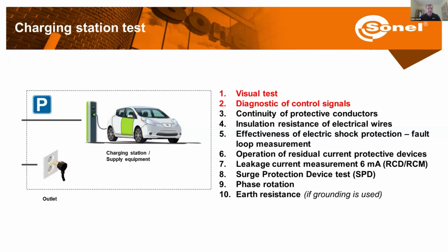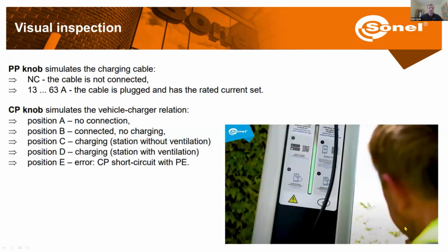Okay, so first let's start with the visual inspection and diagnostic of control signals. For the visual inspection, we check with all our senses to make sure that the charging station was constructed properly, that the right equipment was used, and that it has been installed in a proper way. And also we will look for any obvious physical damage. So that's the visual inspection. Now on some meters you may find a checklist with different items that we need to verify.